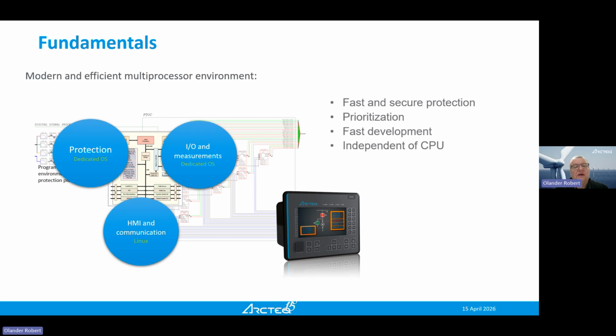We have 3 processors inside. We have a dedicated processor for protection. So in case of some failure on some other part, the protection is the last one to still function, still give the functionality. Then we have a dedicated processor for I/O handling and measurements, and then we have a dedicated processor and a very light Linux system for the HMI and communication on the devices. So here you can see the words are of course fast and secure. That's clear. That's what we are aiming at. But the prioritization is also quite unique. I think that we can guarantee functionality of the protection actually quite deep.